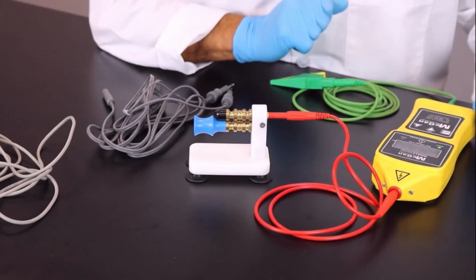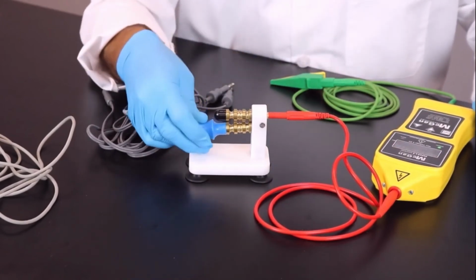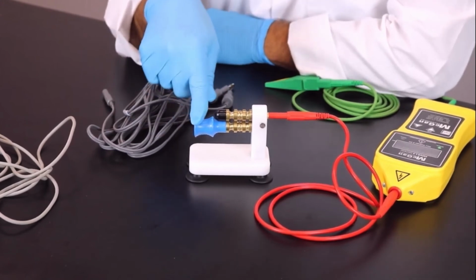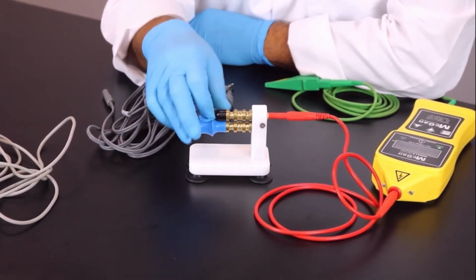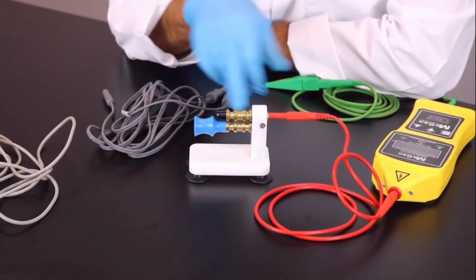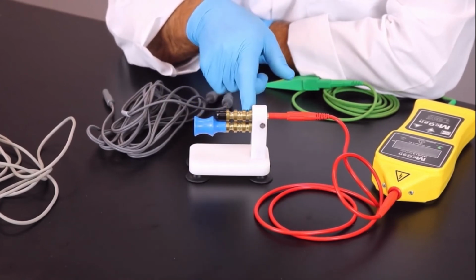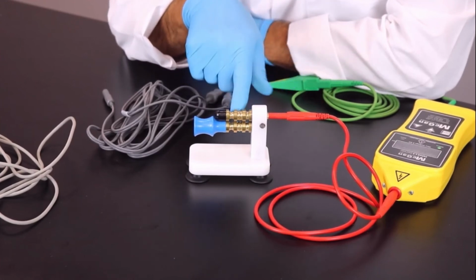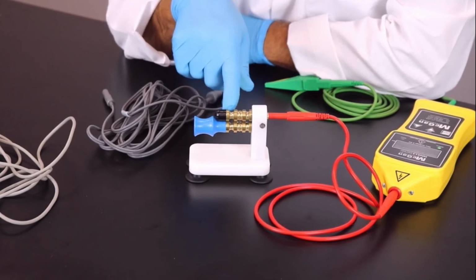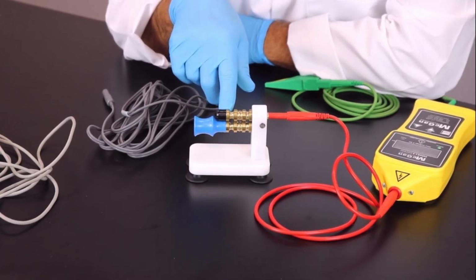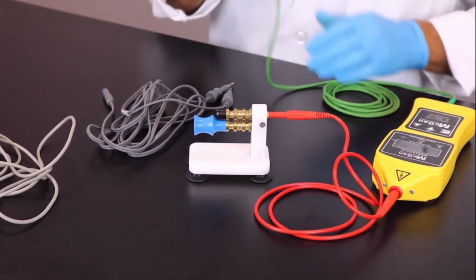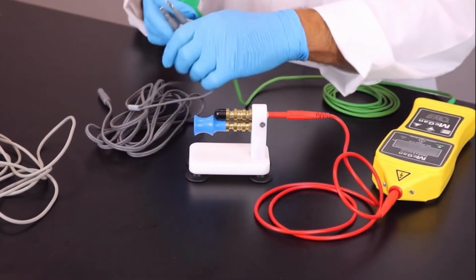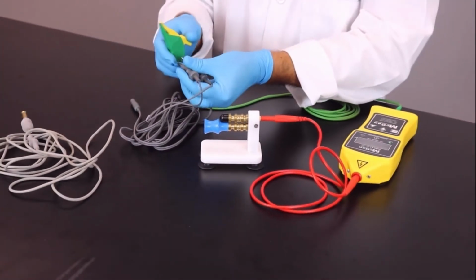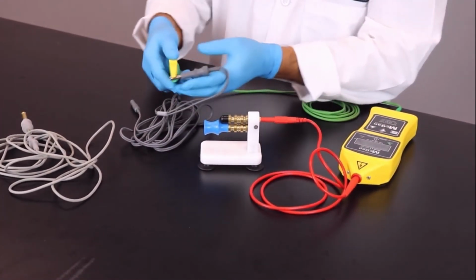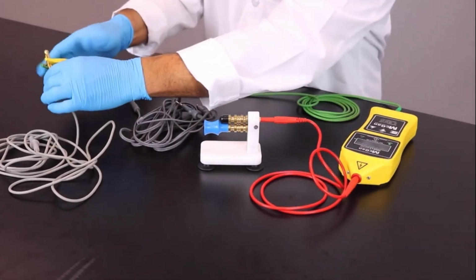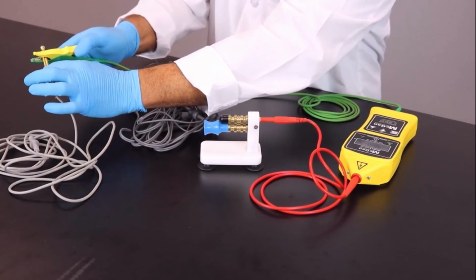After you have everything hooked up for this wire testing unit, let's talk a little bit about the unit itself. So you're going to push down this blue handle and you're going to see what I've exposed is 3 different diameters for cables and cords. The first one you're going to see is a little bit thinner, so that's for a single smaller diameter monopolar cord. The middle will be for a bipolar cord, and this last one is for a thicker in diameter monopolar cord as well. One of the key things to remember is when you're grounding. So if you're using a bipolar cord to test, you want to make sure that you ground both of the leads, like so. If you're grounding the monopolar, it's as simple as just grounding that one piece.